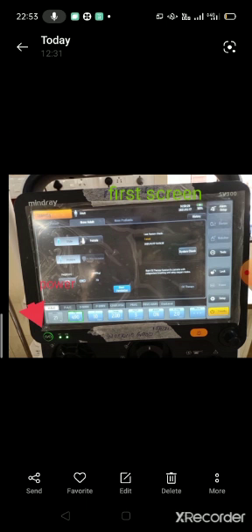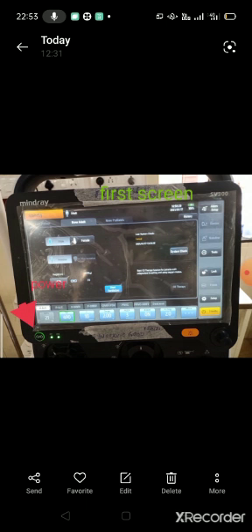When it is shown in orange or yellow color, it means it will be running on battery. What happens is the ventilator will be running on battery when you switch on, and when the battery drains completely, the ventilator will switch off. That is the case when we get a complaint that the ventilator switched off in between. So please ensure, whichever equipment it be, not only the ventilator, that the green color LED is there when it is connected to power. So that is one thing.